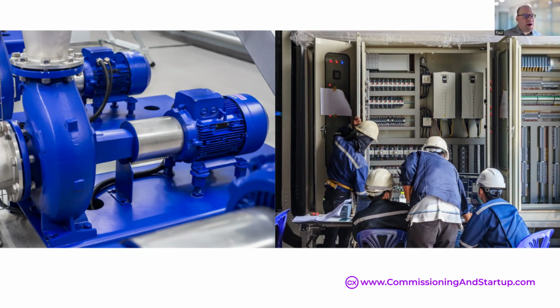When proper FAT and IFAT is implemented in your industrial commissioning process, you're finding problems much earlier in your project development cycles, and you're going to save time during on-site testing. Even with that advanced upfront time for IFAT, you're going to be much more confident that you're getting systems that work when they arrive at site. But when you're skipping factory acceptance testing, thinking you're saving time and money, you'll invariably encounter delays later that cost you even more. Your project gets delayed and you'll miss your in-service date every time. You'll end up leaving too much risk to the end of your project when it's a lot more expensive to fix.